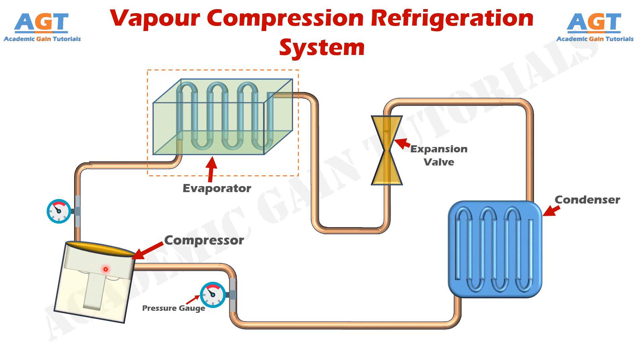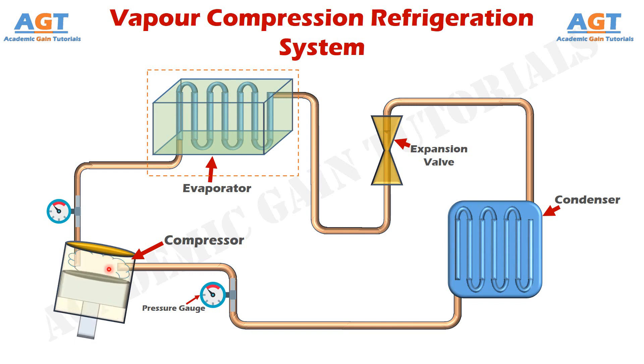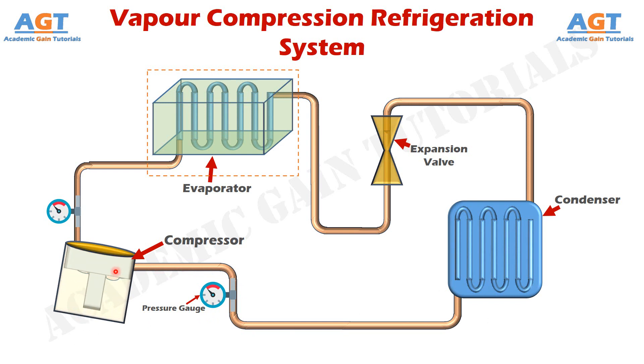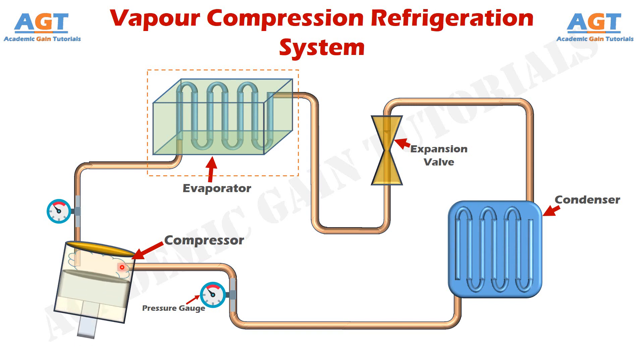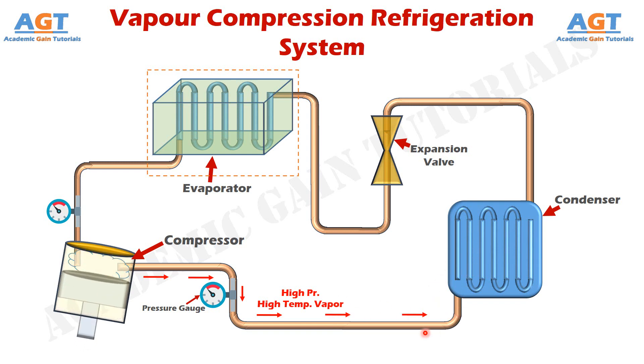First, the compressor starts working. Its job is to pressurize or compress the vapor refrigerant inside the compressor chamber. In the vapor compression refrigeration system, we commonly use either ammonia or Freon as the heat-carrying medium. We know that when pressure increases, temperature also increases. So, when the vapor refrigerant is compressed inside the compressor chamber by squeezing the vapor tightly together, it heats up. This high pressure and high temperature vapor refrigerant then leaves the compressor and enters the condenser through the connected pipe.